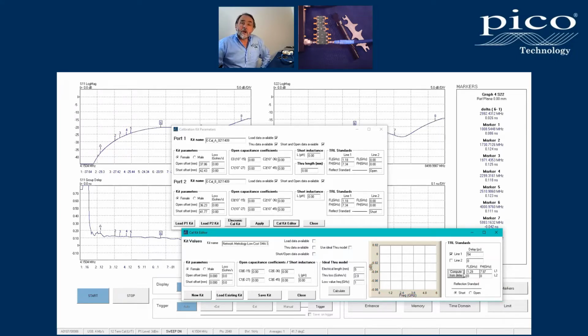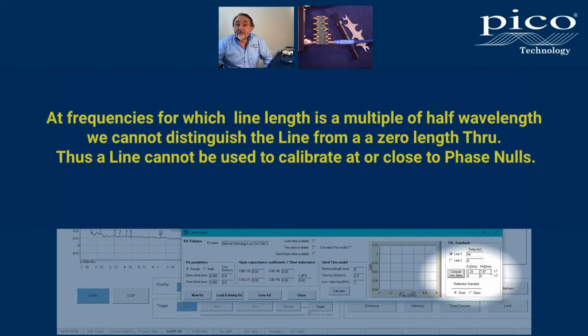Those two numbers come about. We are looking to use our line to calibrate a frequency band, ensuring that we do not approach phase wrap points for the wave in the line. So this figure here tells us that 54 picoseconds of line will leave us with 150 degrees of phase shift at 7.97 gigahertz.